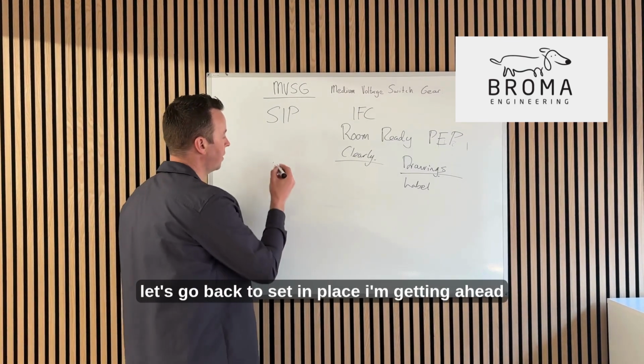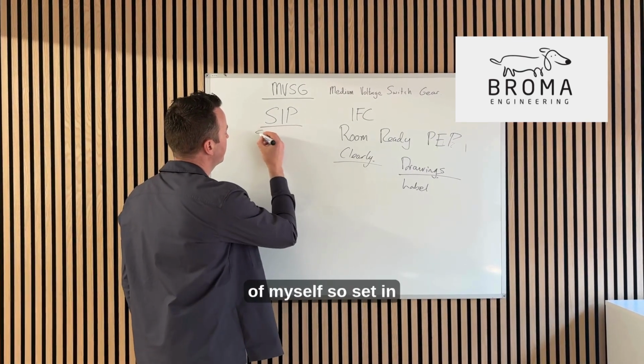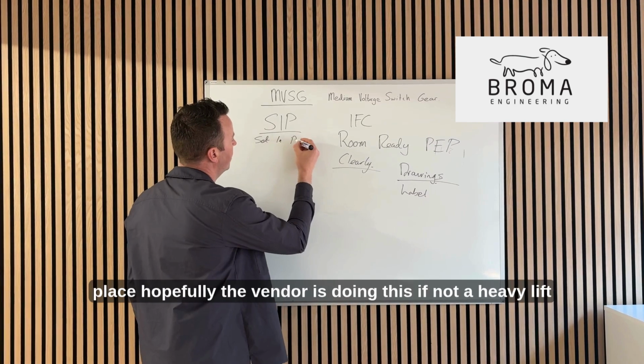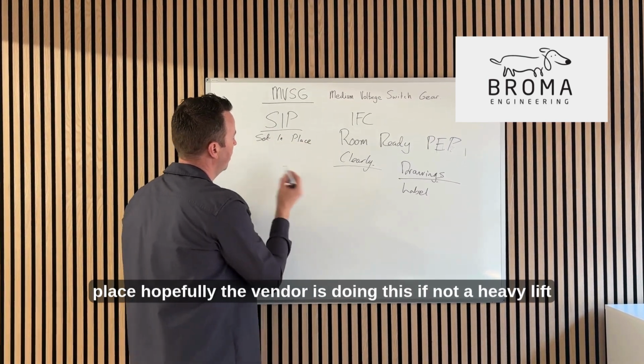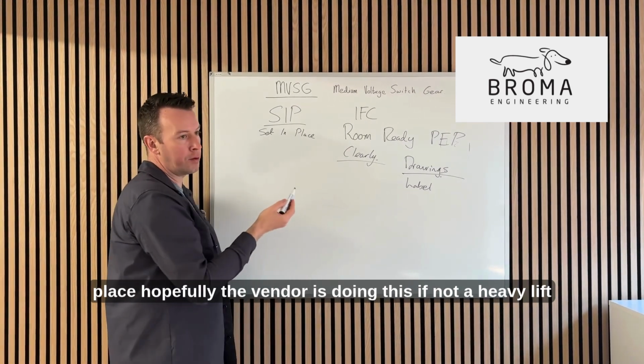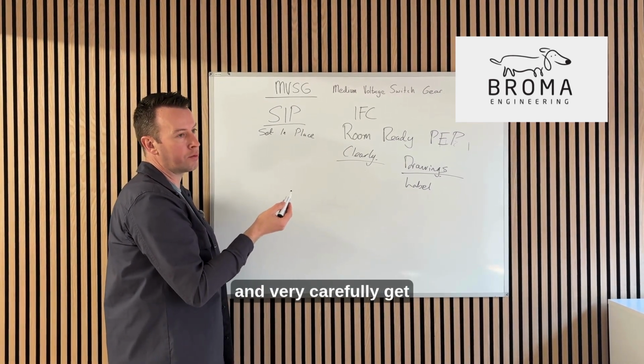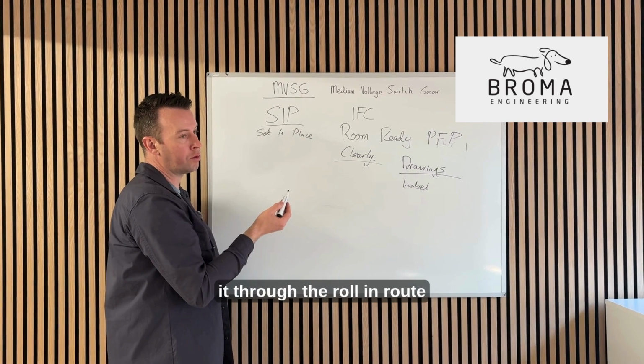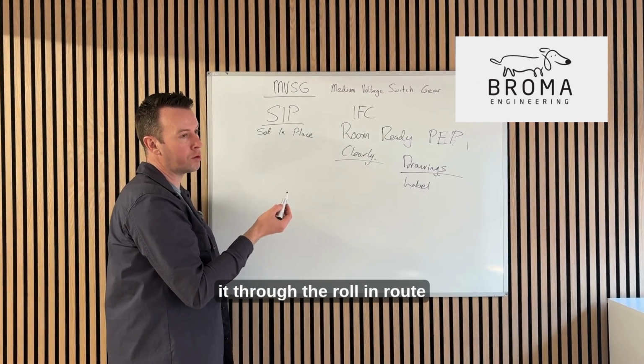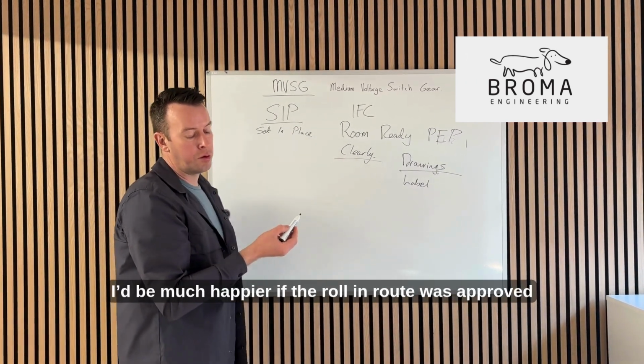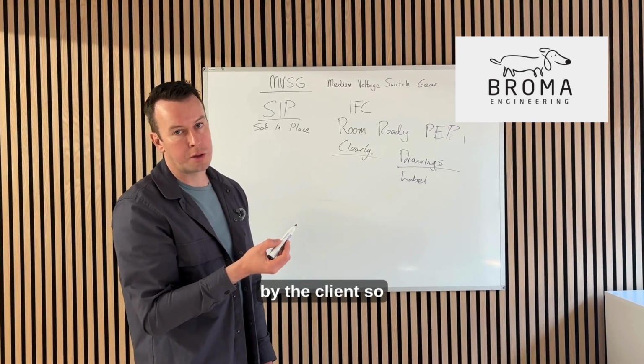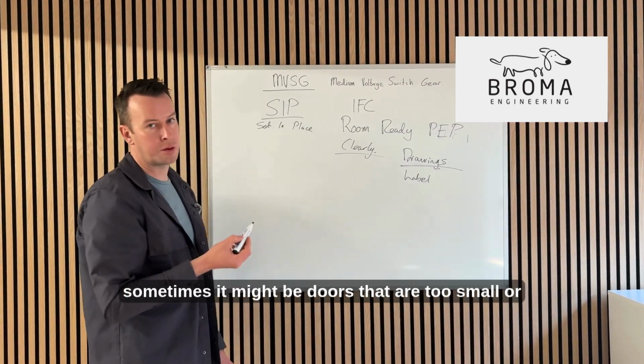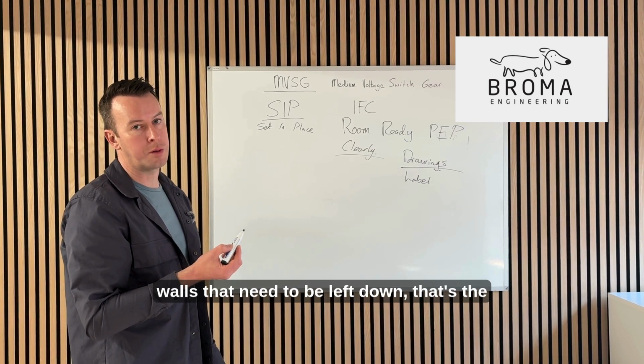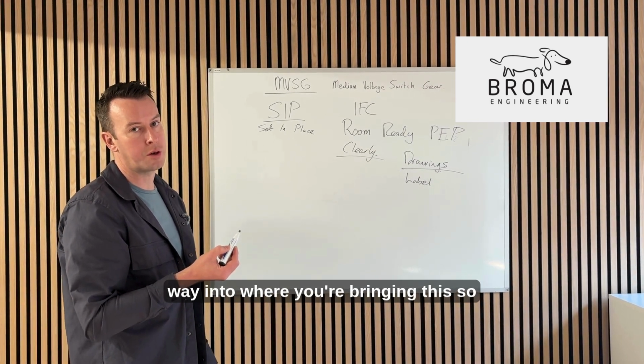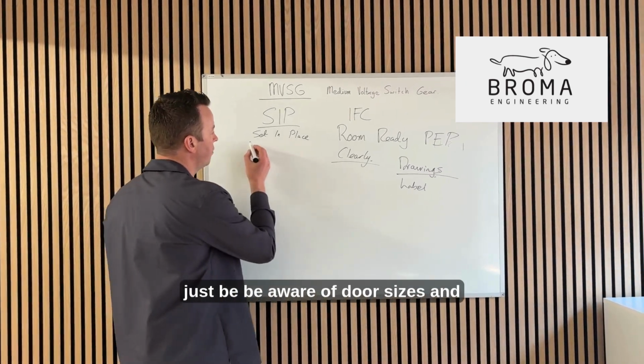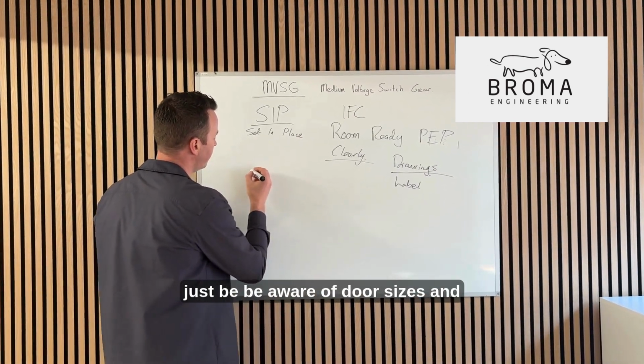But let's go back to set in place. I'm getting ahead of myself, so set in place. Hopefully the vendor is doing this. If not, a heavy lift and shift crew will have to move it into place and very carefully get it through the roll-in route. I'd be much happier if the roll-in route was approved by the client. So sometimes there might be doors that are too small or walls that need to be left down all the way into where you're bringing this. So just be aware of door sizes.